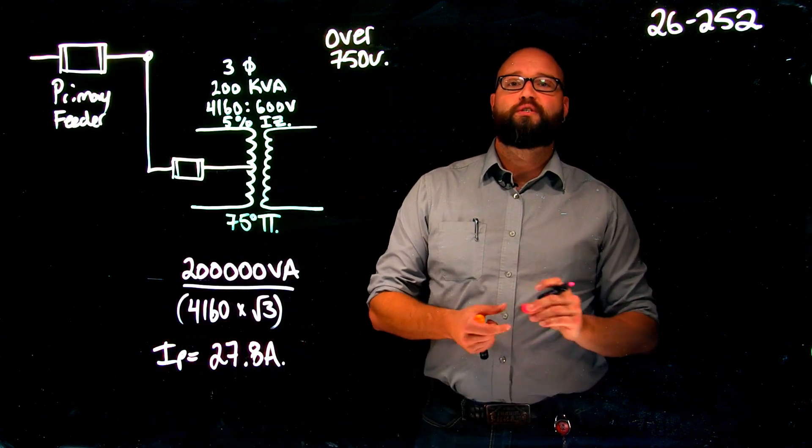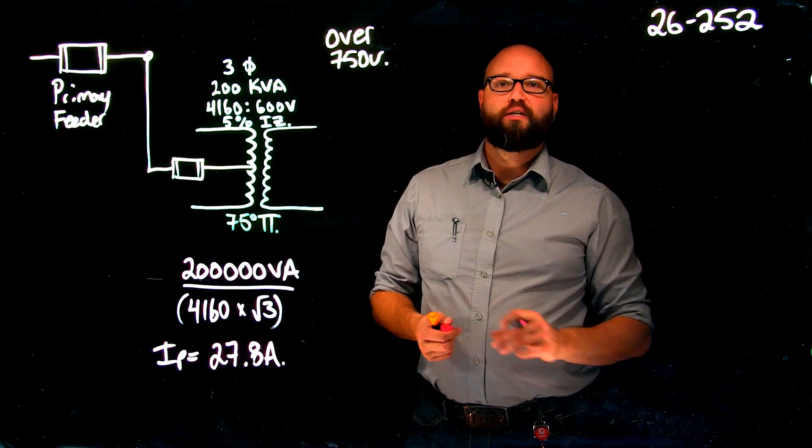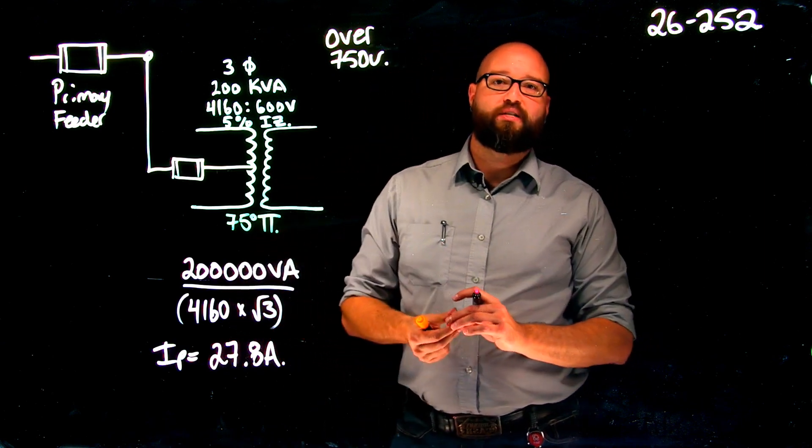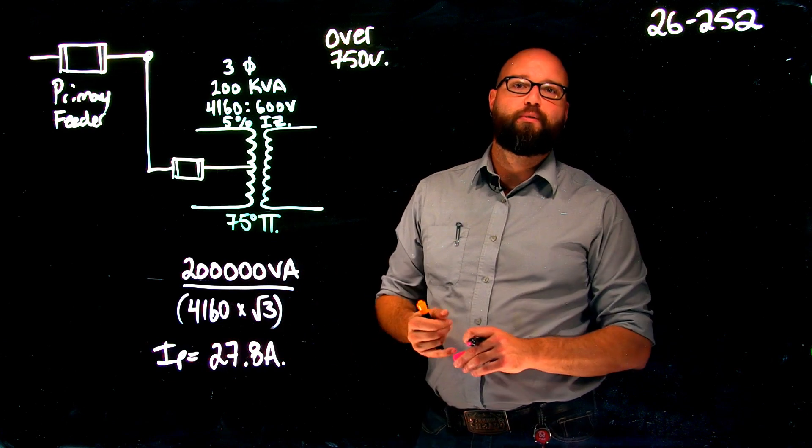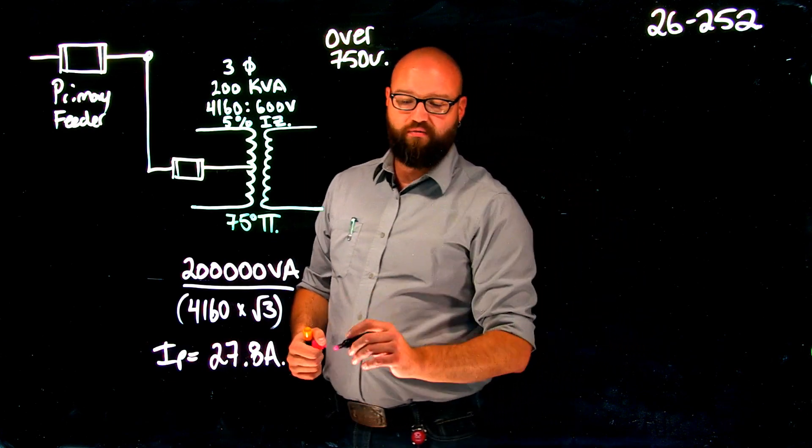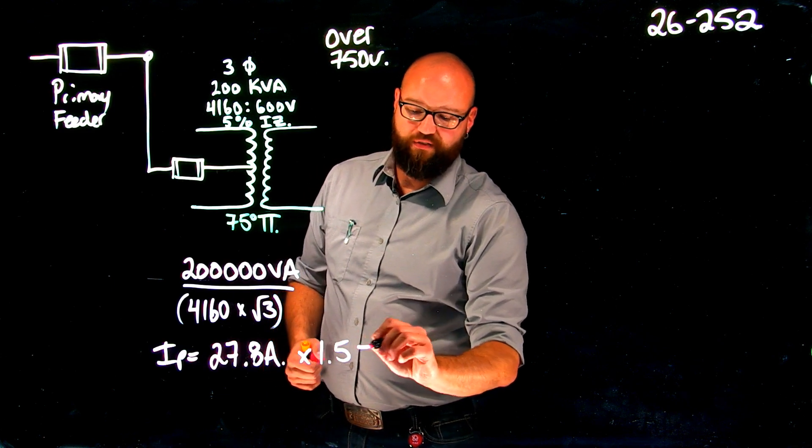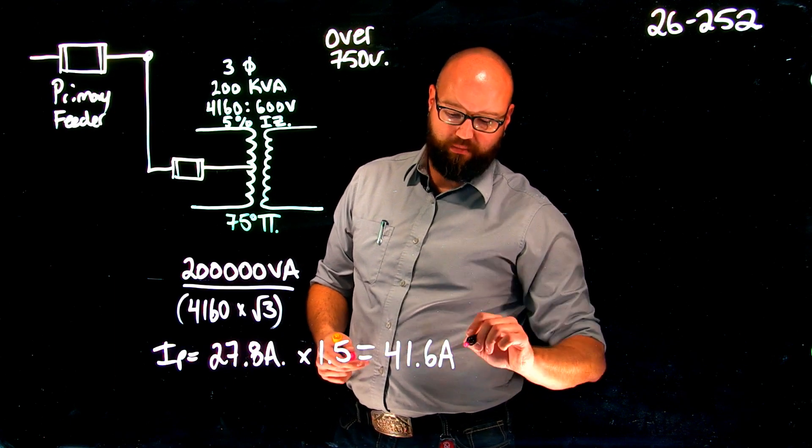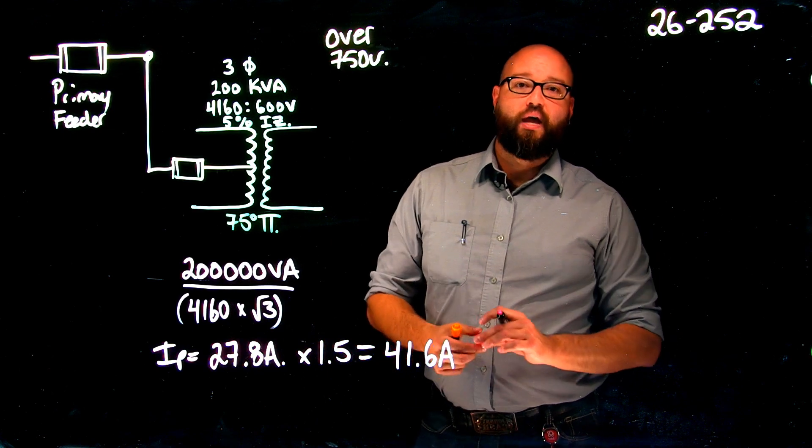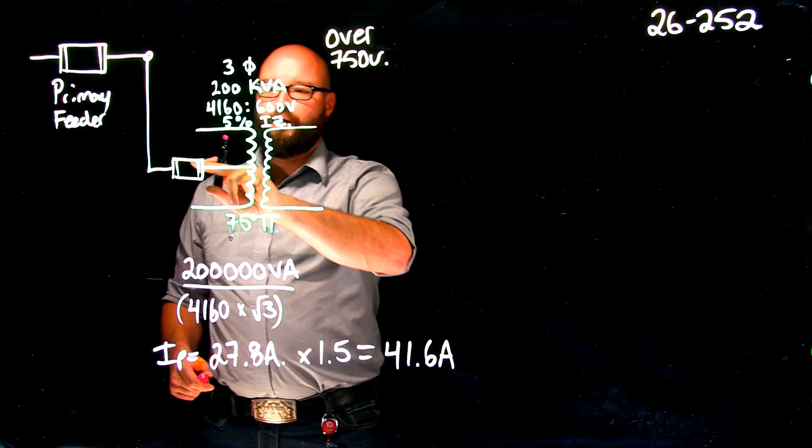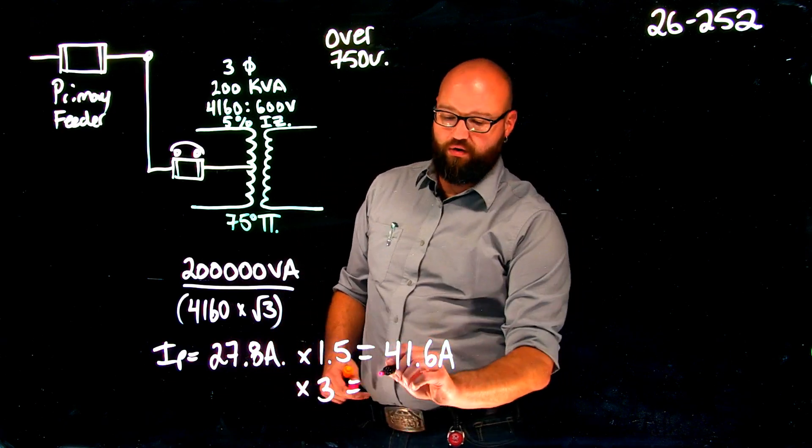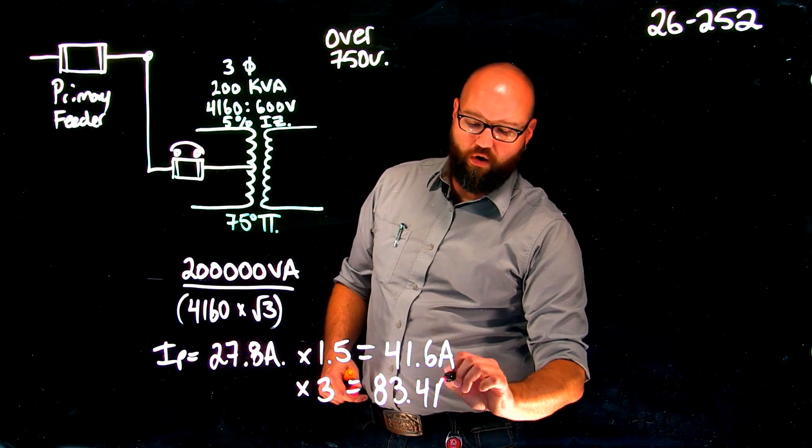26-252 sub-rule 1 tells me if we have primary protection to our transformer only, we are going to take that number and multiply it by 1.5 because it shall be set at not more than 150% of rated primary current, which in this case 27.8 times 1.5 gives me a rated value of 41.6 amps in the case of a fuse. If we are dealing with a breaker, we would use times three or 300%, which gives me a rated value of 83.4 amps.